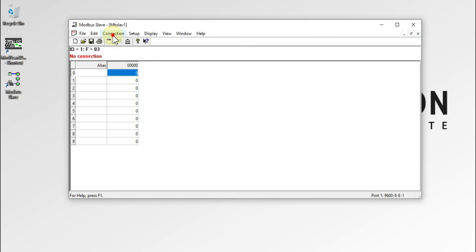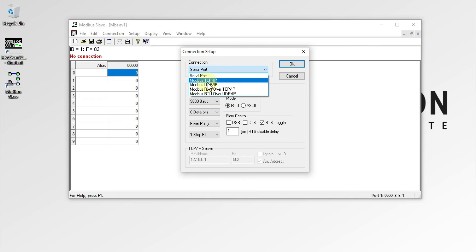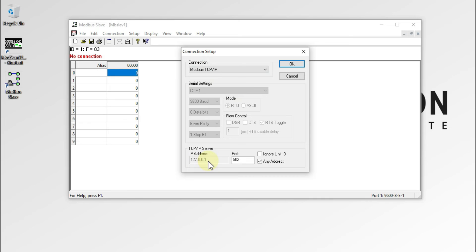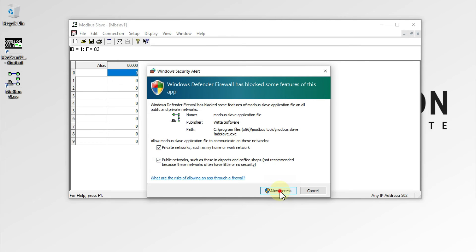To bring the server up, go to Connection and click Connect. Instead of serial port, select Modbus TCP/IP connection. The IP address is shown, the port number is 502 which is standard for Modbus, and tick the checkbox 'Ignore Unit ID' so clients with any unit ID will connect to the same Modbus TCP server. Press OK — the warning disappears. Allow access on the Windows Security Alert so the software can access your private network.